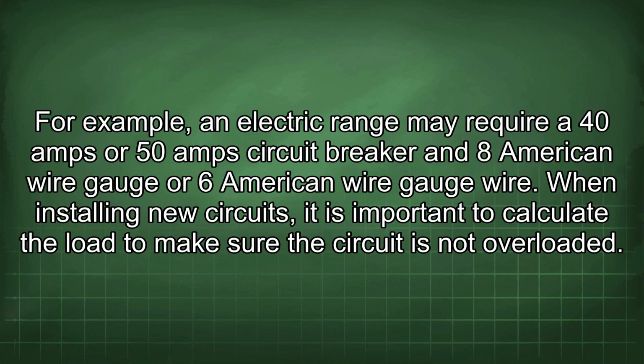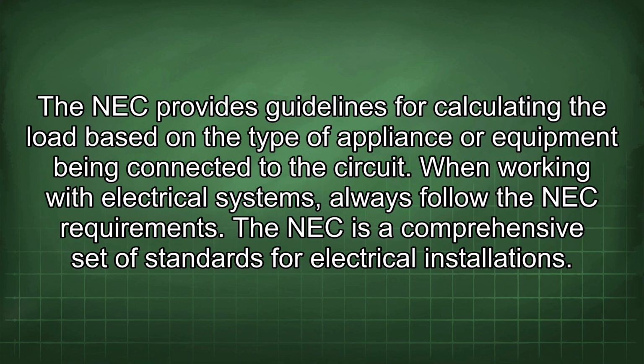For example, an electric range may require a 40 amp or 50 amp circuit breaker and 8 American wire gauge or 6 American wire gauge wire. When installing new circuits, it is important to calculate the load to make sure the circuit is not overloaded. The NEC provides guidelines for calculating the load based on the type of appliance or equipment being connected to the circuit. When working with electrical systems, always follow the NEC requirements.